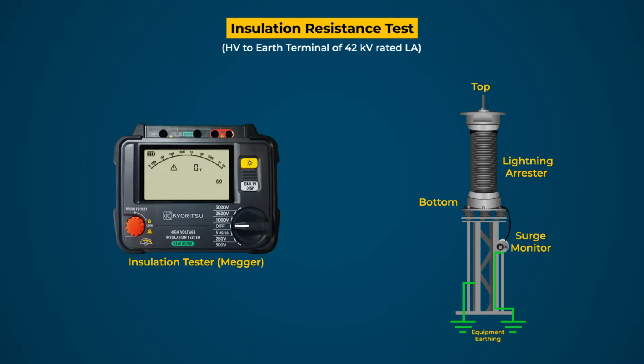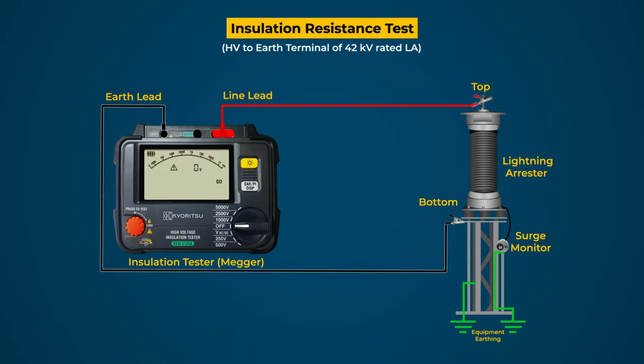Steps for testing. Here we are conducting a test for HV to earthing only for 42 kV rated LA. So for this, first, open the connection at the HV side. For this test, connect the lead of the line terminal of the tester to the HV terminal and the lead of the earth terminal of the tester to the equipment earthing. After that, check all the connections and select the DC voltage level to 2.5 kV in the tester. Finally, the setup is ready to perform the test.